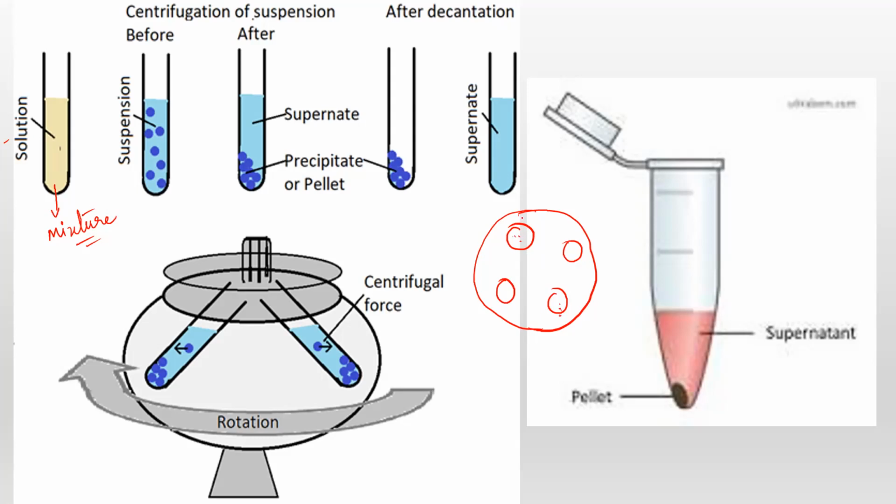Okay, if you keep one tube here, then you cannot start the centrifuge with the other tube kept in the neighborhood. Here you will have to keep the two tubes opposite to each other, so that you're balancing the weight. Okay, also, you must always take two tubes. You should never start the centrifuge with one tube. Always start the centrifuge with at least two tubes, an equal number of tubes.